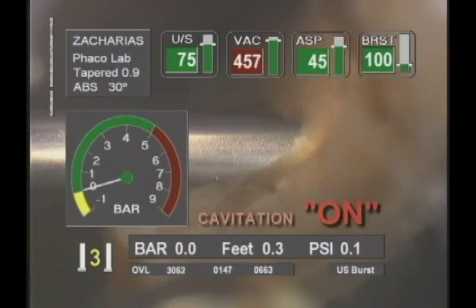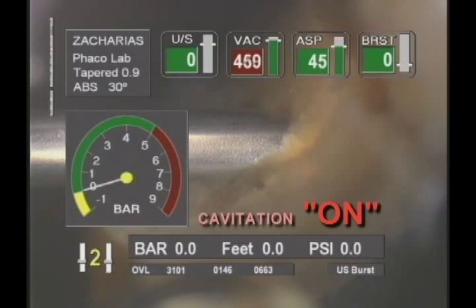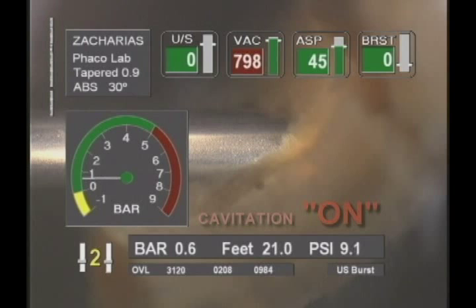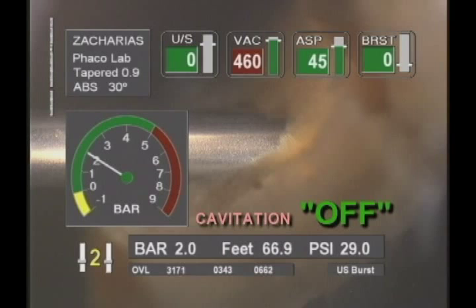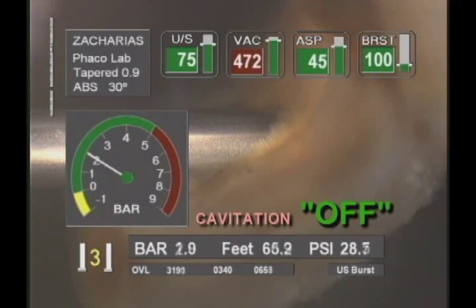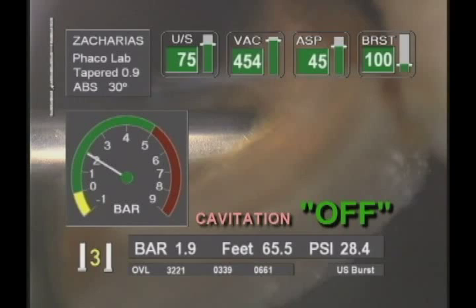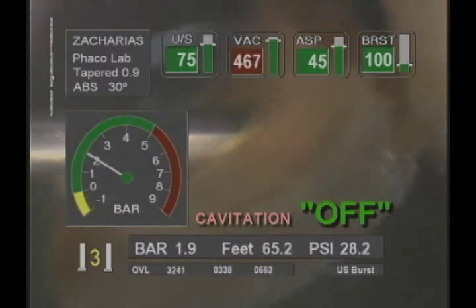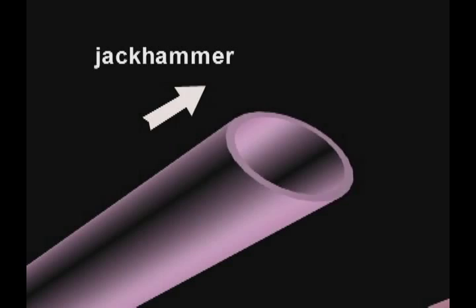Finally, we have determined that with acoustic cavitation totally suppressed, the phaco emulsification action is unaltered. The fact that phaco occurs when no cavitation is present provides strong evidence that cavitation plays no role in phaco emulsification, leaving the jackhammer effect as the only mechanism responsible for the lens-disrupting power of phaco.